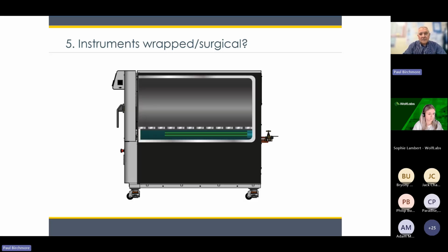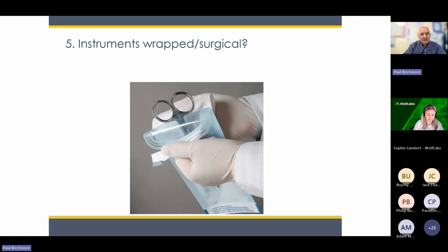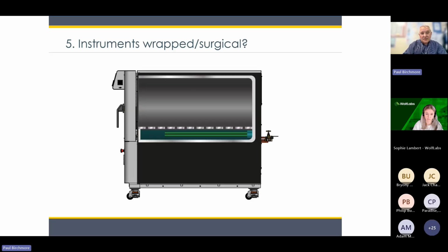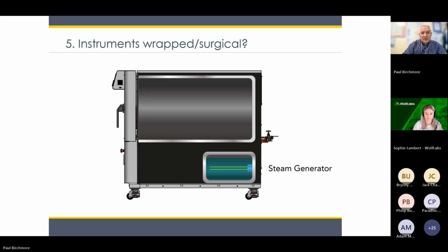So what we wouldn't be able to use for this type of item, which you can see here in a porous pouch, is a wet autoclave. What the pouch will do is prevent any physical contamination of the item when it comes out of the autoclave before it's used in a surgical operation. But you've got a barrier there, and that barrier has to allow steam to penetrate in to decontaminate the sterile item. But at the same time, that porous membrane will remain moist at the end of the cycle in a wet autoclave. So we can't use this type with the heating elements inside and the wet conditions inside the chamber. We need to prevent that.